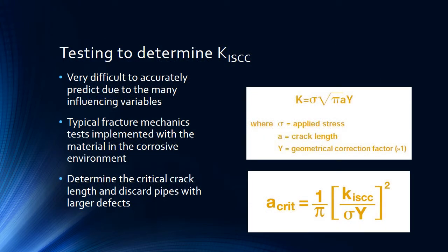It's very difficult to accurately predict the stress intensity factor at which stress corrosion cracking will occur. However, typical fracture mechanics tests are implemented, except the specimen will be placed in that corrosive environment. Once this critical value is determined, a critical crack length can then be determined as well, and pipes with larger defects than that can be discarded.